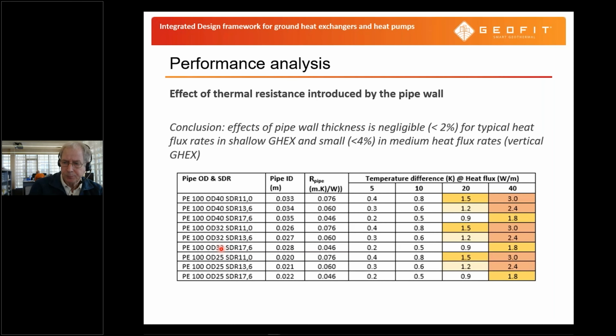If we take a little bit closer look at the effect of the thermal resistance introduced by the pipe wall material itself, because of course you can think, can we use other types of material that have a higher thermal conductivity? So we zoomed in a little bit on that, and here you can see that we've considered different types of polyethylene material, different diameters of the pipe, different SDR. It stands for the standard dimension ratio. So it means that if you have a 40 millimeter pipe, the wall thickness is 40 divided by 11.